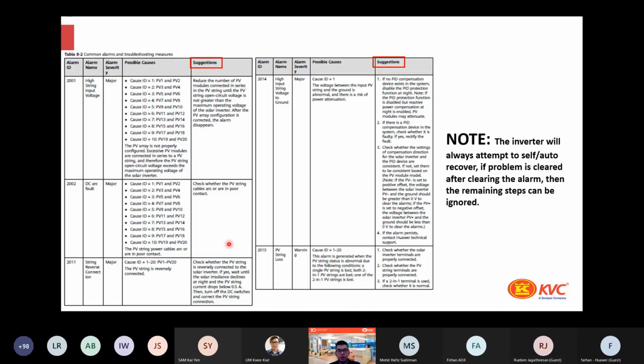So one key important thing I need to highlight is that the beauty of the Huawei solution is that the inverter will always attempt to self auto-recover. Going back to my earlier part about grid over voltage, the reason the inverter intermittently turns on and off is because it has already self-recovered. So often when there's an alarm, you won't even notice in the first place because the inverter has already auto-recovered. Once again, this minimizes your need to go to site to do maintenance checking or any form of checking on your inverters. That's the beauty of our solution, the inverter always attempts to auto self-recover.